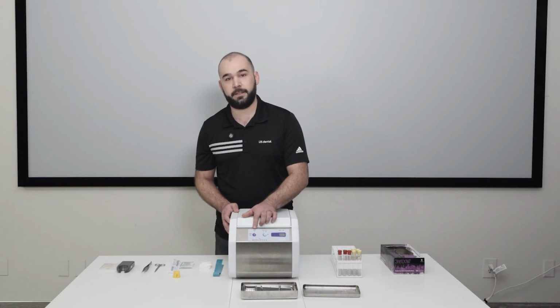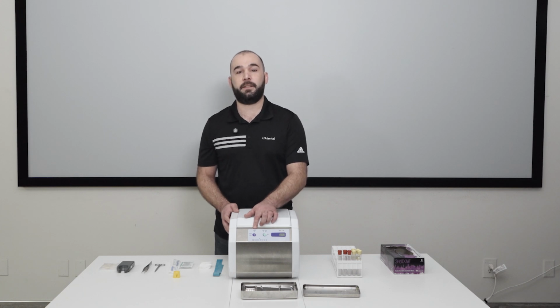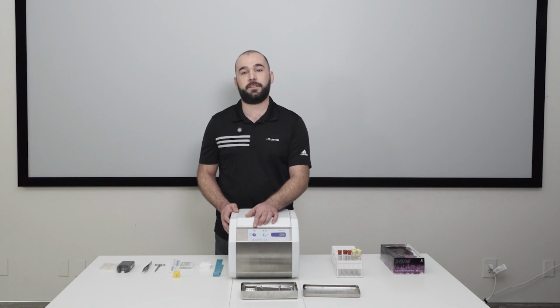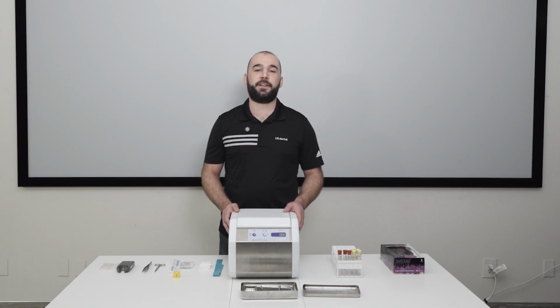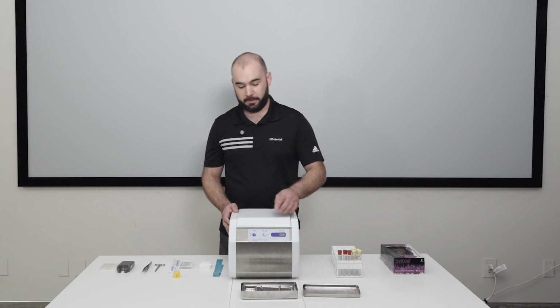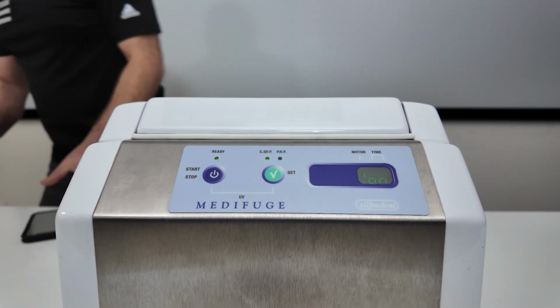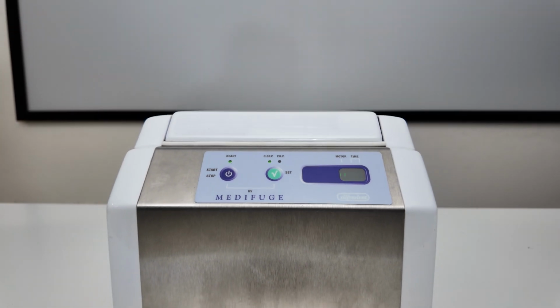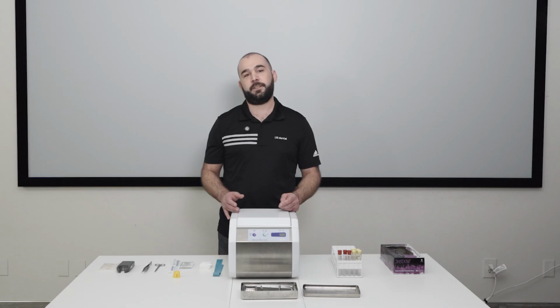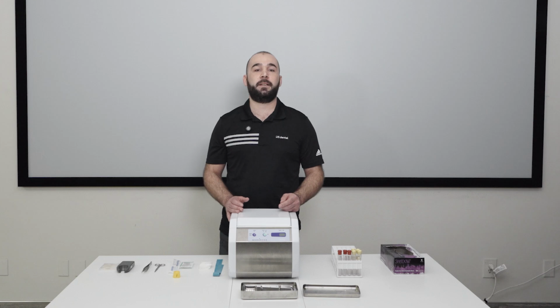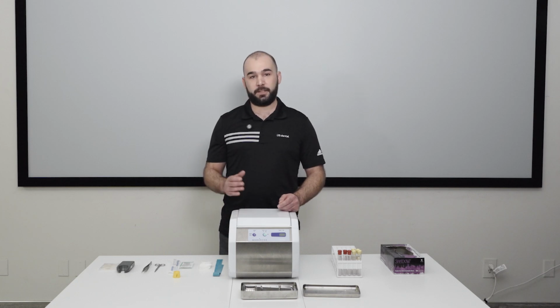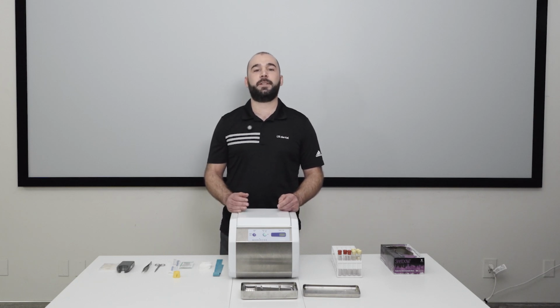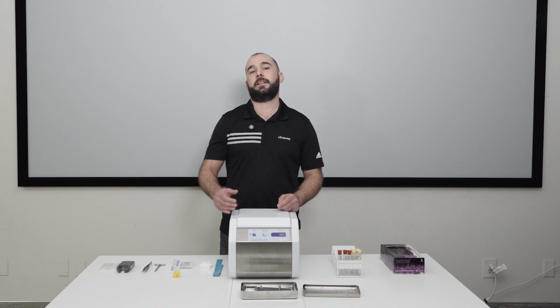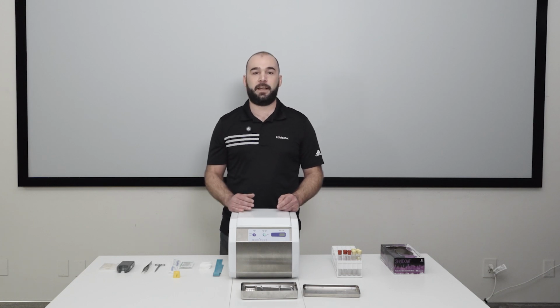The purple button is for starting and stopping the centrifugation. It's straightforward. Press it once to start the spinning, and if you need to interrupt the process at any point, just push it again. Let me show you how it works. Press the button once and it will start spinning. If you listen closely, the sound will change, as the machine is uniquely designed to offer a multi-speed centrifugation process. This will allow you to collect approximately 1.7 times more growth factors than conventional PRP or PRF.